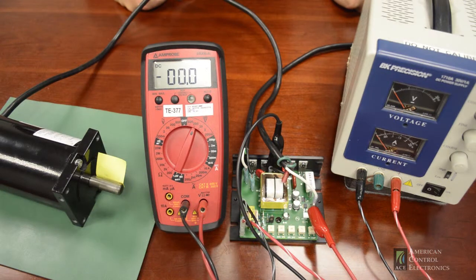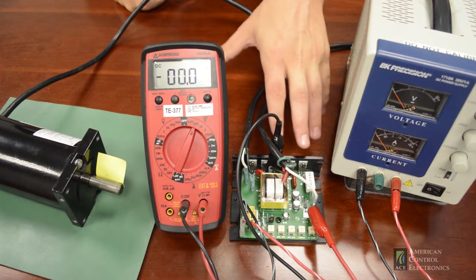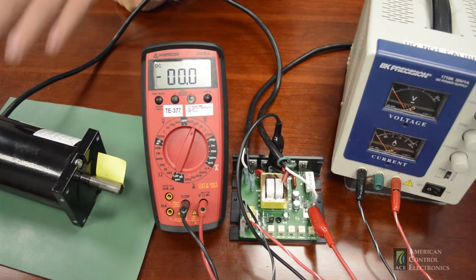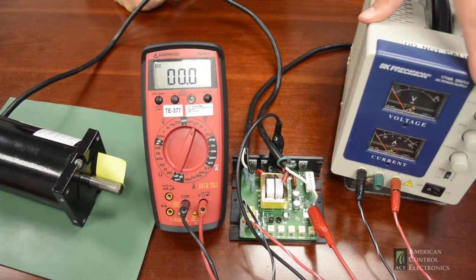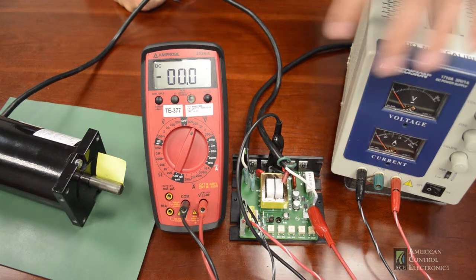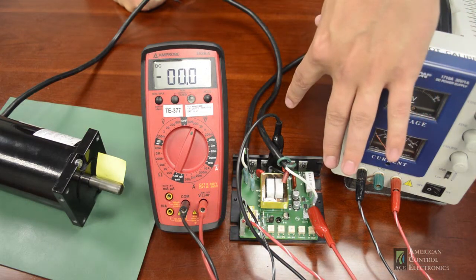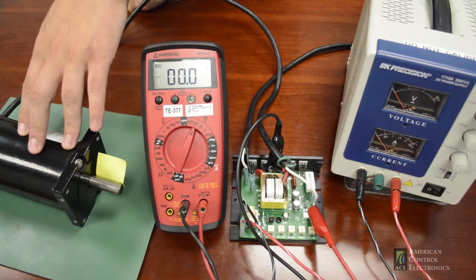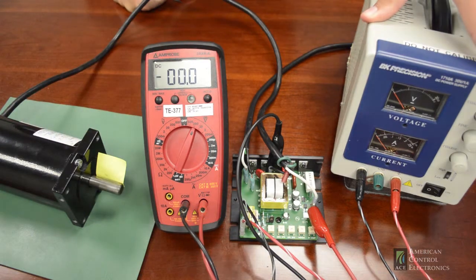The signal adjust trim pot adjusts the maximum voltage the drive will output to the motor when applying your maximum voltage input signal. To calibrate the trim pot we must read across A1 and A2 the voltage the drive is outputting to the motor and we must apply our maximum voltage input signal.